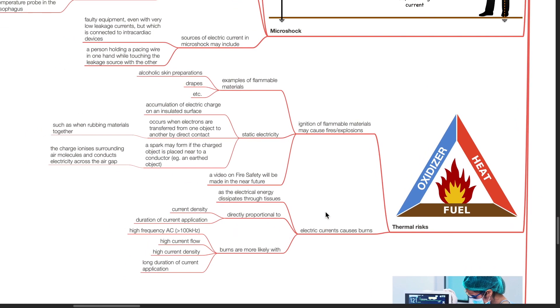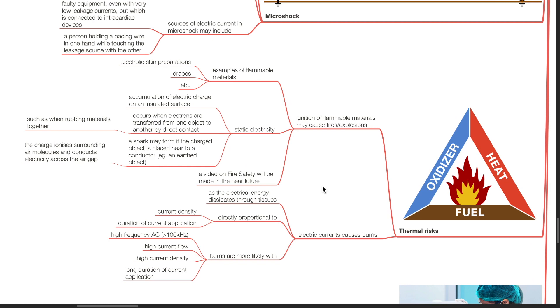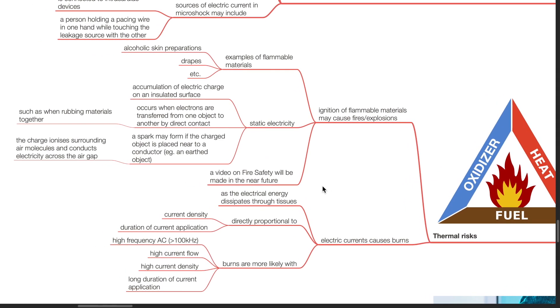Thermal risk. Ignition of flammable materials may cause fires or explosions. Examples of flammable materials include alcoholic skin preparations and drapes. Static electricity refers to accumulation of electric charge on an insulated surface and occurs when electrons are transferred from one object to another by direct contact, such as when rubbing materials together. A spark may form if the charged object is placed near to a conductor, such as an earthed object. The charge ionizes surrounding air molecules and conducts electricity across the air gap.